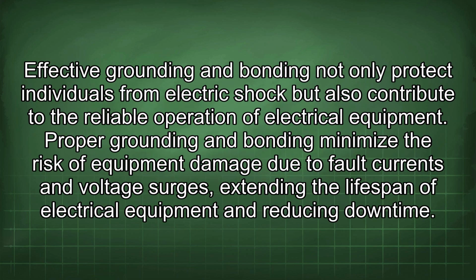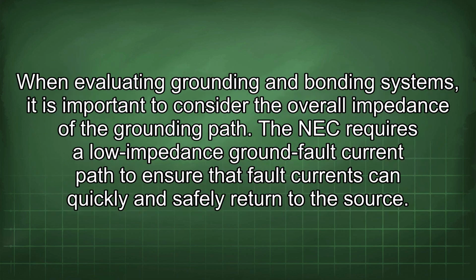Effective grounding and bonding not only protect individuals from electric shock, but also contribute to the reliable operation of electrical equipment. Proper grounding and bonding minimize the risk of equipment damage due to fault currents and voltage surges, extending the lifespan of electrical equipment and reducing downtime. When evaluating grounding and bonding systems, it is important to consider the overall impedance of the grounding path.